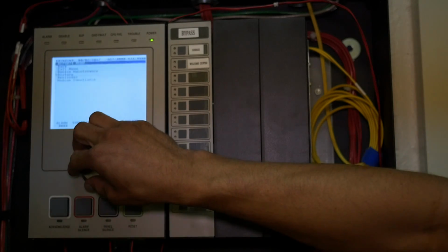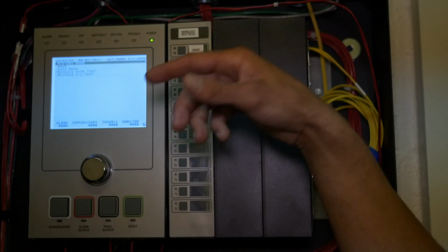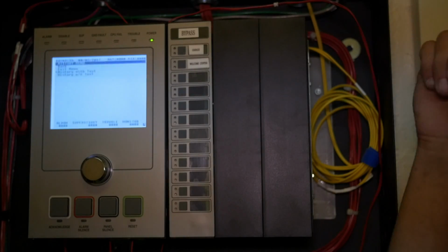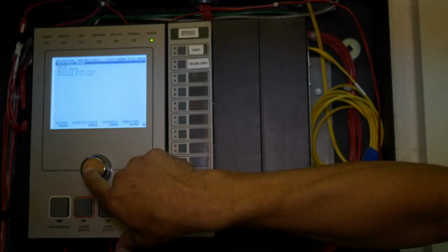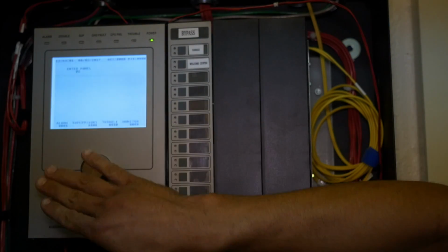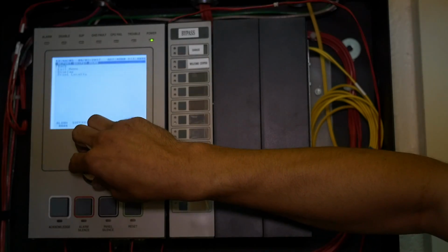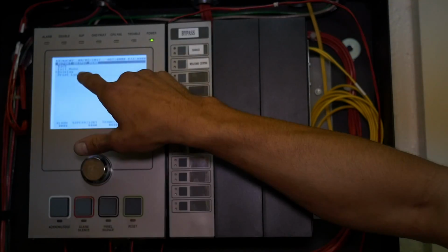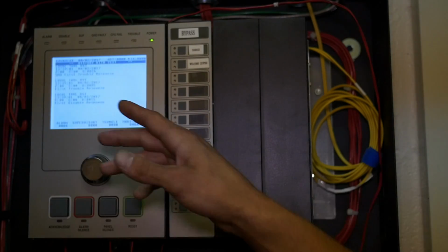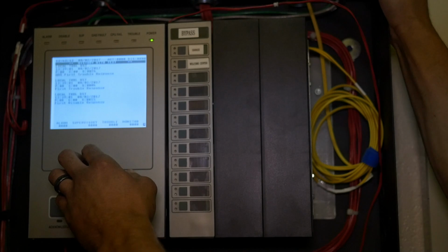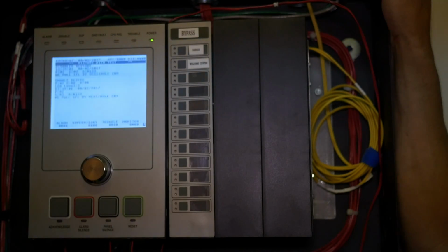The history, you can look at history on this panel or the network panel up in the maintenance garage. You'll have to go to history with text, enter. This is panel 2, so we want to look at the history on this panel, enter. Display, there's no printer, so you cannot print it. You'll just hit enter on display. And this will go through and give us all of the history up until the last time that the history was reset, which I don't think it's been reset yet.